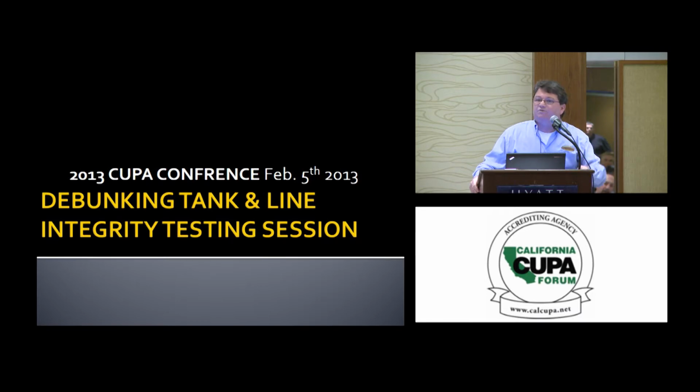Tank testing is prescriptive. We're coming in there to take a look at your tank. By the way, how long is the test good for? Anybody? If I go out and test your tank today, how long is that? You already know that answer. The minute I drive away from the location, it's over. Seriously. So don't think it's good for a year. That may be a compliance thing because you have paperwork for a year, but that test is not good for a year. Both technology and ourselves have been saying this since we're blue in the face. We leave, and 6 months later they say there's a problem. We find out that there was a gardener cutting into the vent pipe. All kinds of different things have happened. We cannot be responsible except for that moment in time.